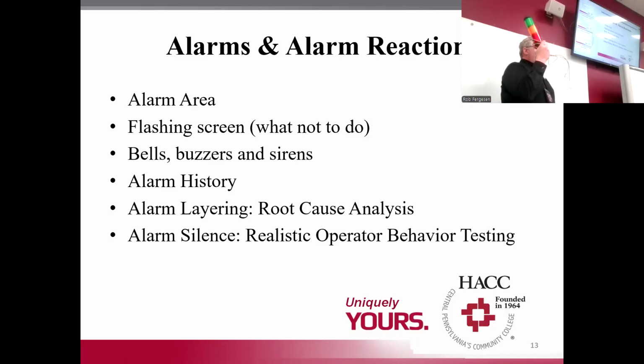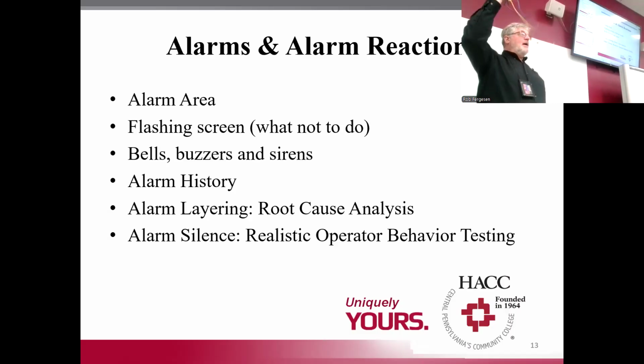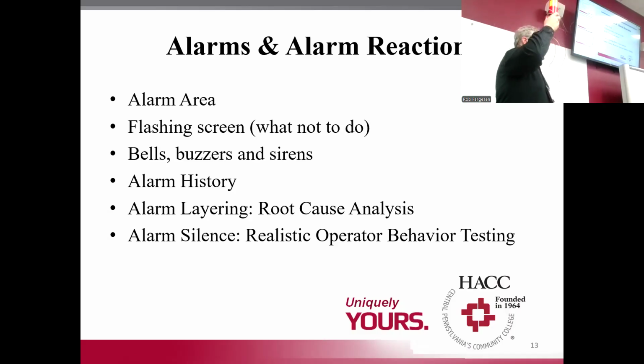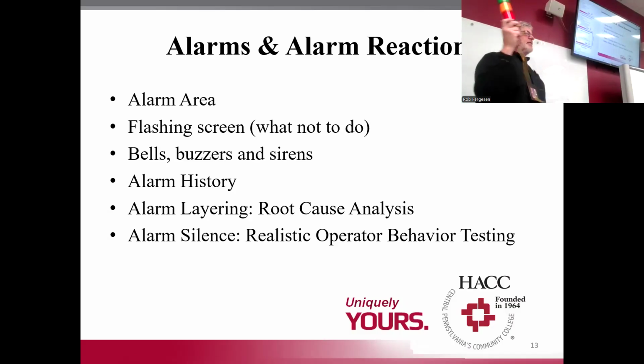This is the best kind of alarm as far as I'm concerned. It's usually not audible. It's usually highly visible. And it's the simplest alarm in the world. Come pay attention to me because my light stack is right above a machine that's got an issue. You got to take care of that issue right now. Right. And that's the only time you should use a light stack is when a machine has an issue that you got to take care of right now. Or in the case of robots, work cells, I've shut down that robot work cell because I got a problem. Take care of me right now. So this is a classic alarm.